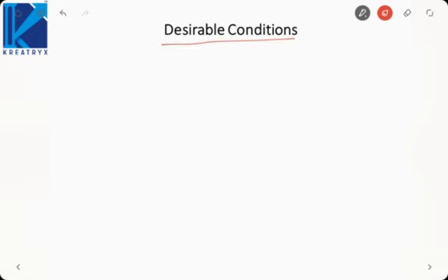Now there are some desirable conditions also which ensure that the transformer operation is well and good. These are not the necessary conditions, meaning even if they are not satisfied it is fine, but if they are satisfied the operation is better. For a better operation we must satisfy these conditions, but it is not that if these are not satisfied the parallel operation is impossible. These do not stop the parallel operation, but they just can make it better.